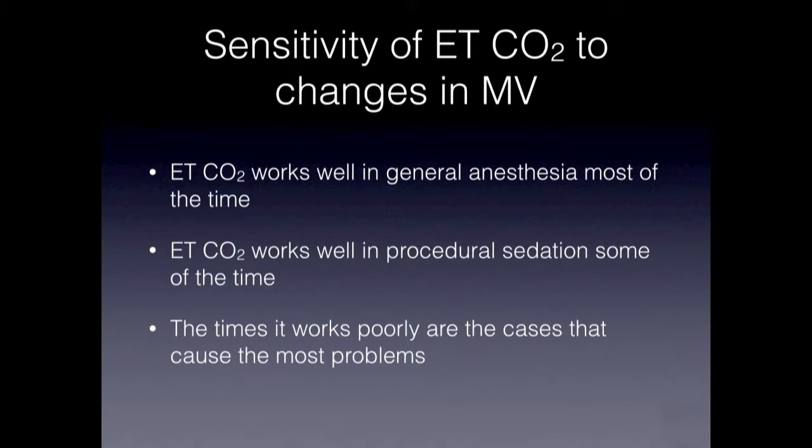Okay, yeah, Jim. What would be a good response to a physician who tells you they don't care what the CO2 number is, they're more concerned about the waveform and the breath rate? To which I say, yeah, you're right, but you can't interpret that waveform that well. People are going to look at that one graph and say, oh, there are 10 breaths there in 30 seconds, the patient is breathing at a rate of 20, when in point of fact there were 3 breaths there, they're breathing at a rate of 6.